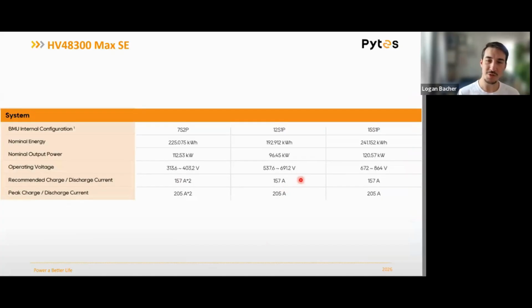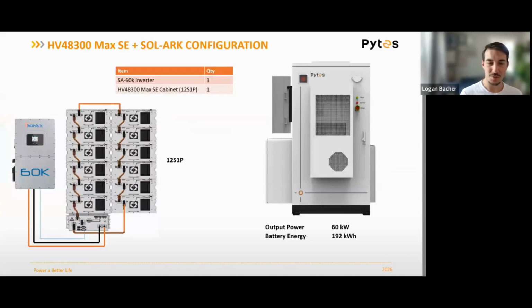The module voltages though are still 51.2. So in terms of the number of batteries in series as a min and max, that's all the same. An example with Sol-Ark 60K, again, 500 volt max input. That means we top out at 12 batteries in series. 12 batteries at 16 kilowatt hours apiece is almost 200 kilowatt hours total, which again, no issue satisfying that full 60 kilowatt output of the inverter.